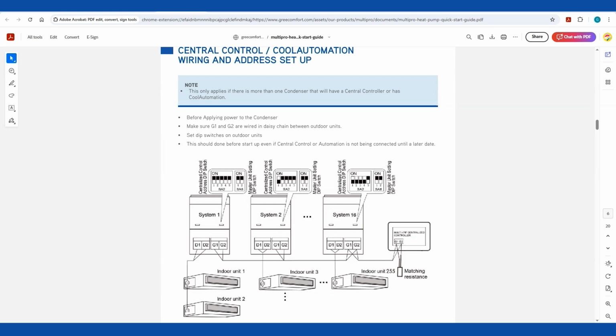You don't have to have the wires going to the controller yet. You can just daisy chain across the units and stop there. Then, and this is before you ever apply power or anything, before you commission the unit, we're going to go in here and set these dip switches so that when you start this thing up, it's going to have unique addresses and we don't duplicate.